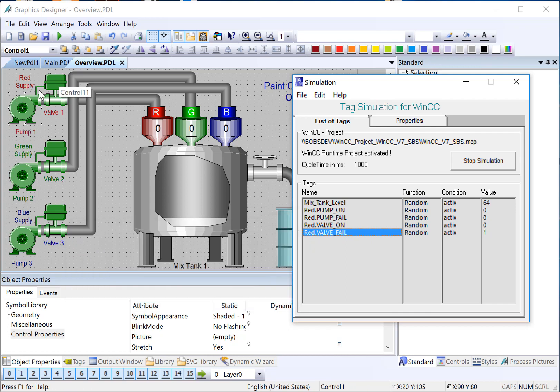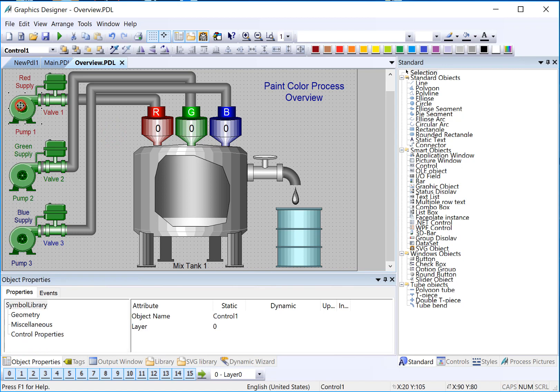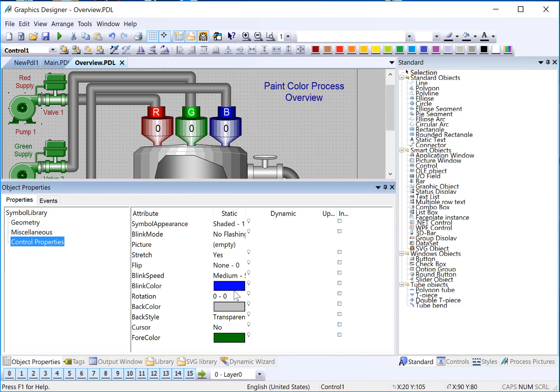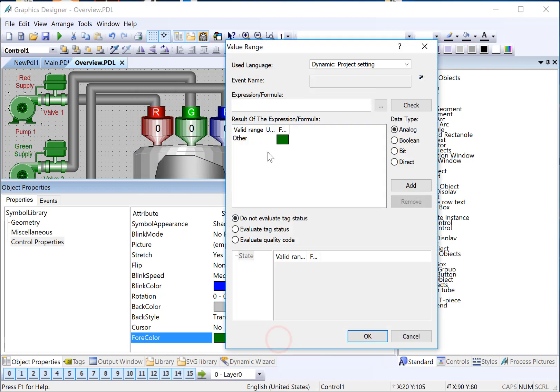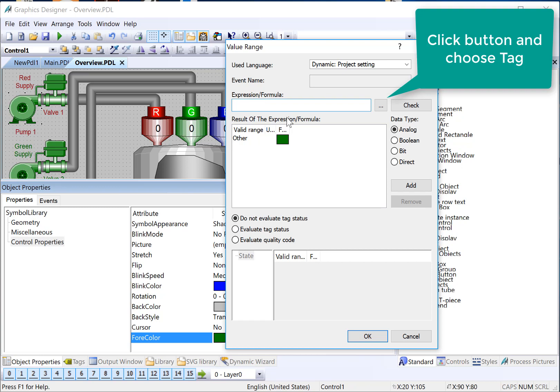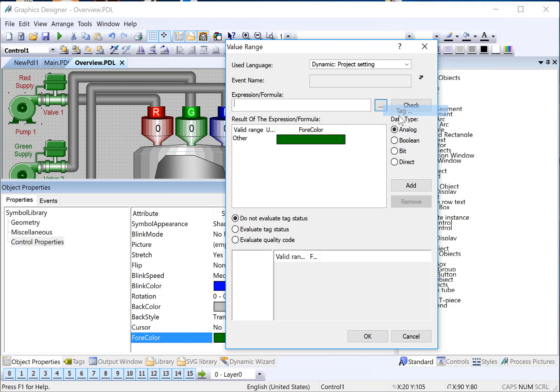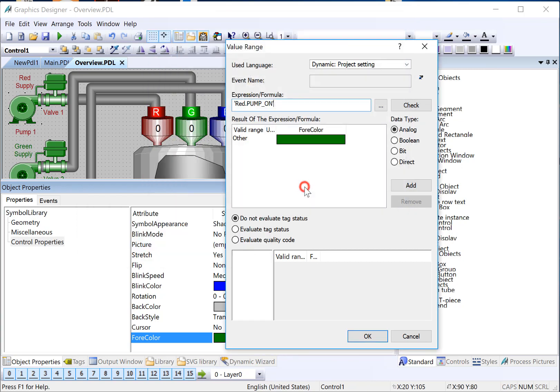Next, we want to use Dynamic Dialogues to change the color. So we'll start with the Pump. I'll highlight the Pump. And the trick here is go find the property that you want to see change. So we want the Pump to appear red if it's on. Red is running. And green if it's off. Green is safe. So under Control Properties, the property that controls the color of this pump is ForeColor, so that's where we go. We're going to right-click on the Dynamic column and choose Dynamic Dialog. So for Dynamic Dialog, it looks at an expression or formula, and then the output of whatever type the expression is is going to set our property. So our expression in this case is just what is the value of our Pump on or off tag. So we'll click the button, choose Tag, and we will find Red Pump on and just click OK.